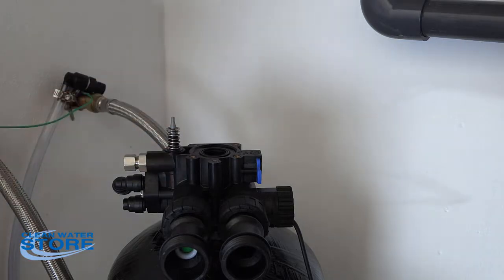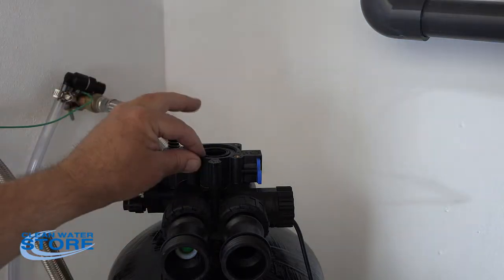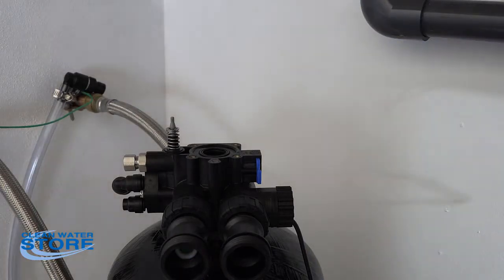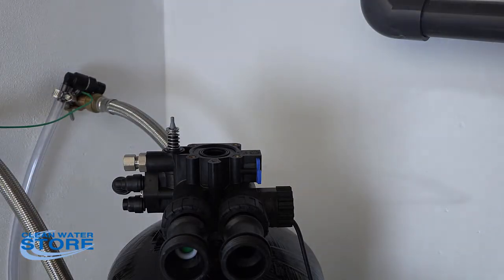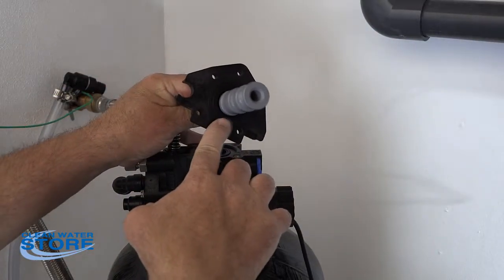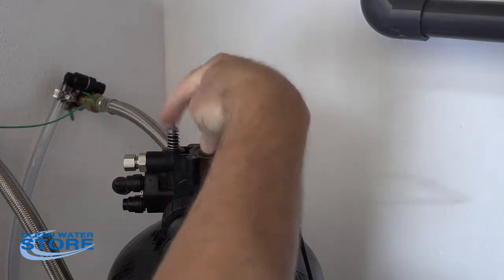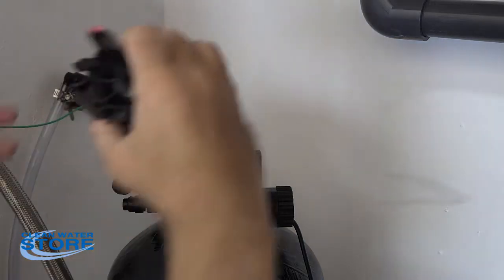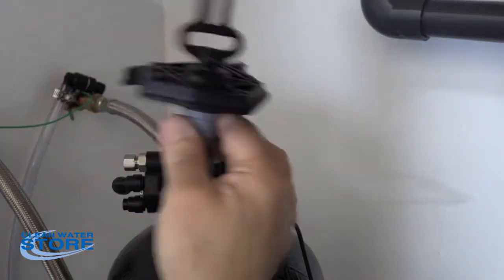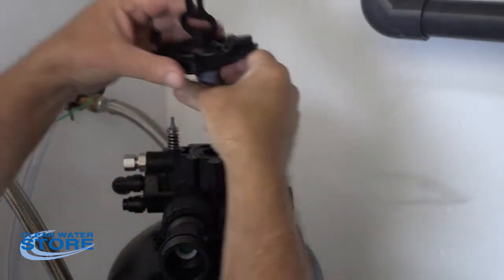Now as you can see here, take note of this kind of depth here. Because the piston assembly here, this part of it seats down onto it. What you want to make sure is if that bottom seat's not oriented correctly, it's going to be up high. As you tighten this down, you're going to break it. So you've got to kind of make sure it all looks like it's going to snug up. Again, wipe, clean up your piston. If your piston's badly damaged, we do sell these new assemblies. You can order one of these from us.